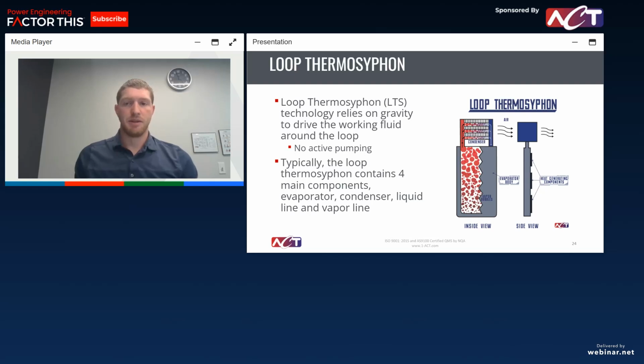And that's going to be taking away all that heat, rejecting all that heat. It's going to move up to a condenser that's located somewhere above it. In this example, the condenser is directly above it, but the one advantage of loop thermosyphon is that as long as your condenser is vertically above your evaporator, it can be located remotely, which is a great advantage. You don't necessarily have to have your whole system in the same area, which, in many applications, you have only a very small space claim for your thermal management. So that's your evaporator, your condenser.